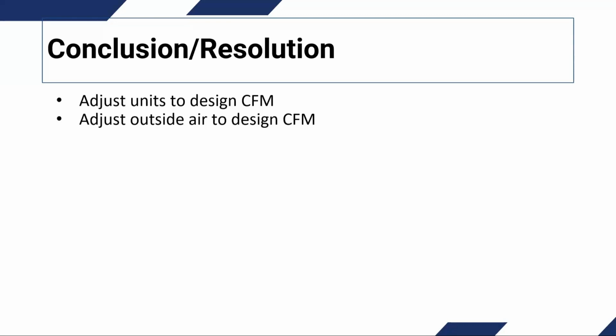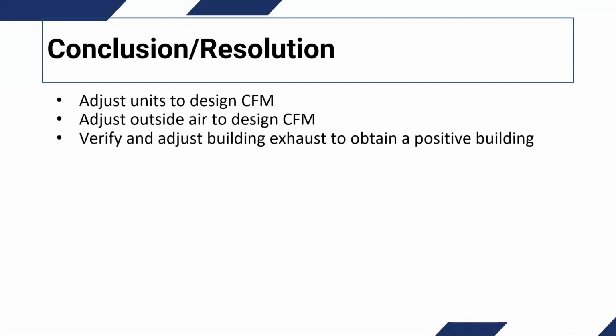We adjusted all the outside air. So we had to go through and adjust the outside air on all the equipment to make sure that the building was getting the right amount of outside air to meet code and to keep the building positive. In doing so, we noticed that even though once we had the outside air set, we still weren't positive. And since we initially were just looking at the humidity issues in the building, we didn't initially take any readings on the exhaust system of the building. But once we had design outside air everywhere, we noticed the building was still not positive. So that resulted in us going back and verifying the exhaust throughout the building and adjusting the exhaust accordingly to make sure that the building was positive under normal conditions.